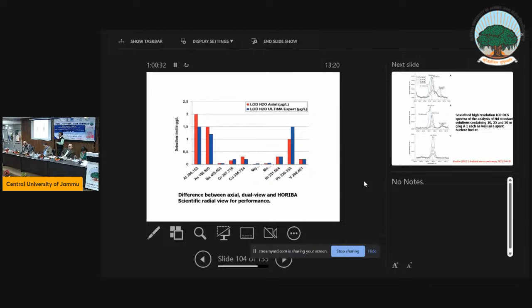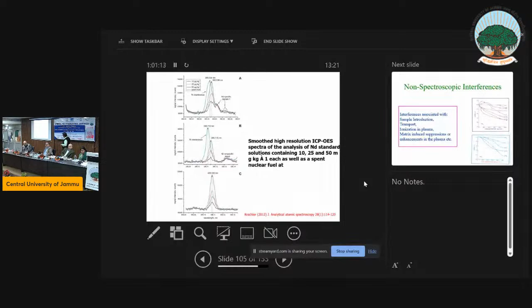Now you look at how this analyst has tuned up the machine. It's not that the machine is doing something. The analyst is playing around with the machine and tuning it. Multiple peaks here to arrive at a single peak is to optimize the flow rate, the argon flow rate, the forward power which varies between 800 to 1500 watts. Flow rate, argon gas, cooling, plasma height, all these parameters you have to think about. Either you take help of literature and try them, or you yourself calibrate it. But this is how, if you are able to put in the analysis, then you can make the clarity in the peaks like this.